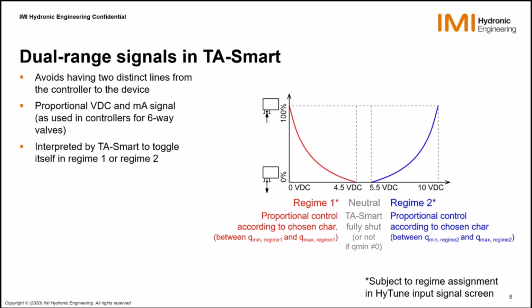And of course, in between these two, we get a neutral area where the TA-Smart is fully shut, but only if the minimum flow is different from 0. So we are getting this use of the dual range, nothing really new except that you will get a characteristic associated to the control mode that you have chosen. A dual range signal is advantageous in that with only one wire, one line, we are able to pass two types of information: how to control the device and in which regime we are.